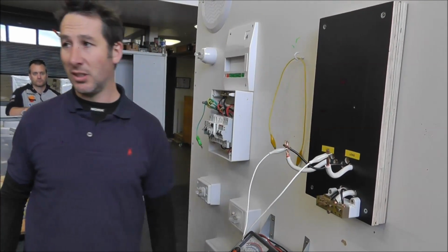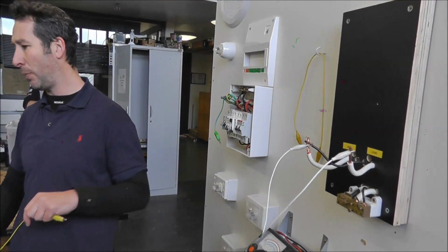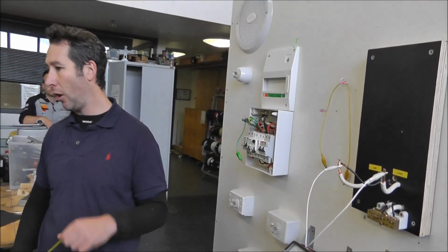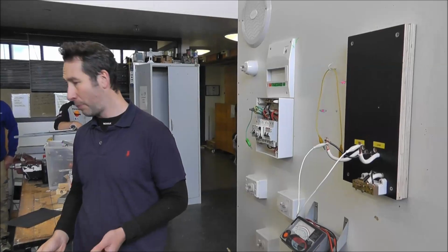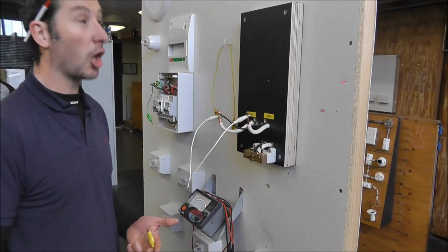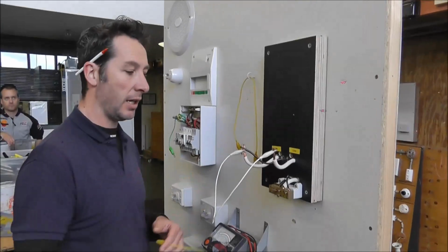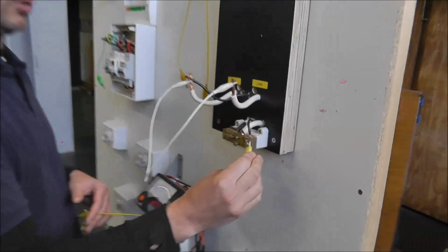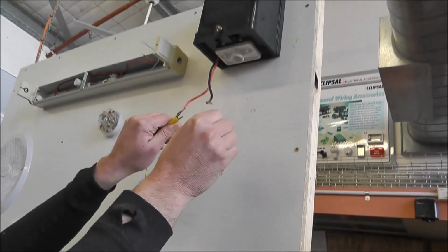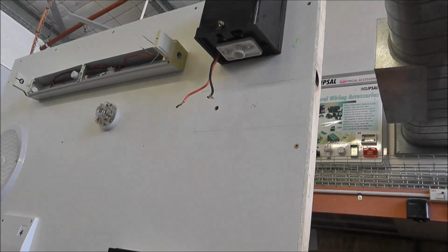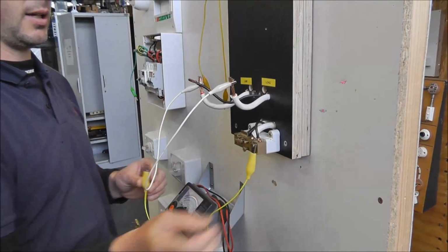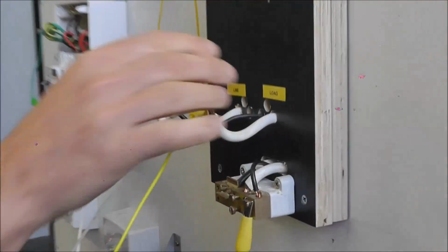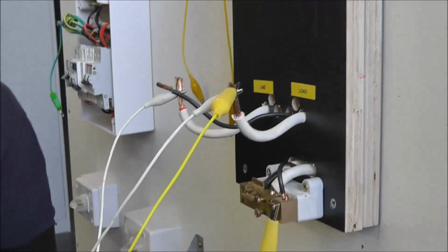What's insulation resistance mean? What have I got to test for? Between what and what? Live parts and earth. So that would indicate that I have to join what? Live parts. I can do that anywhere. I can do that up here, do it here. I'm just going to do it here because I just like to do it here. You could theoretically do it here. I don't know why I don't like to do it there, I just don't. I'm going to join up neutral here. I'm going to join up to the active there. So now I've got live parts connected.